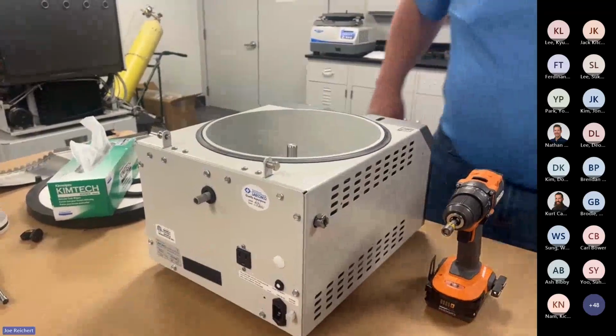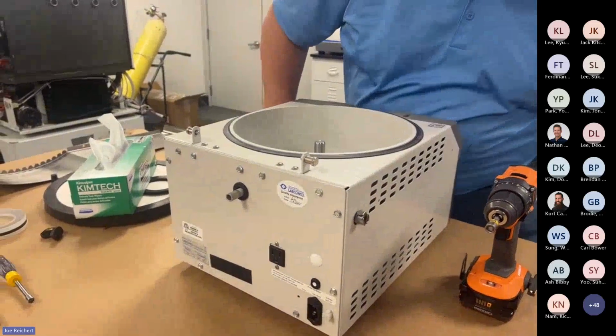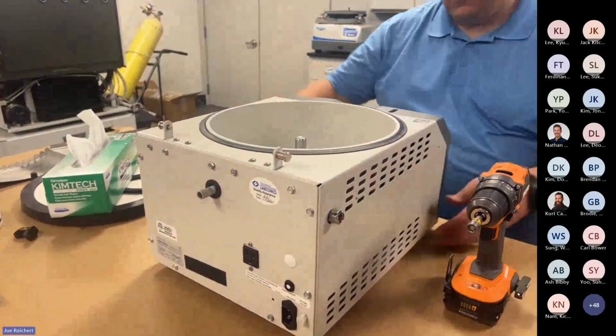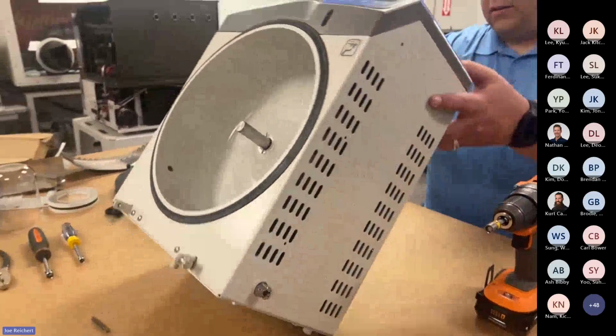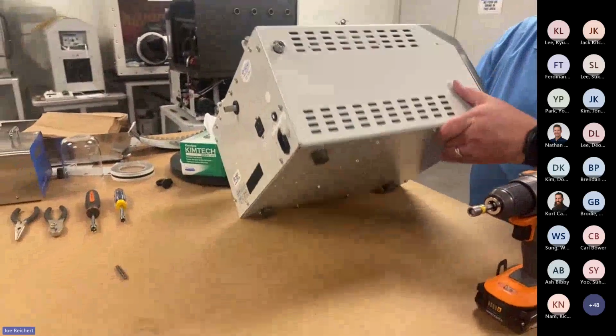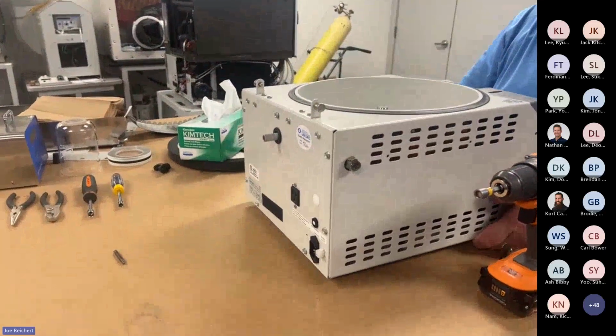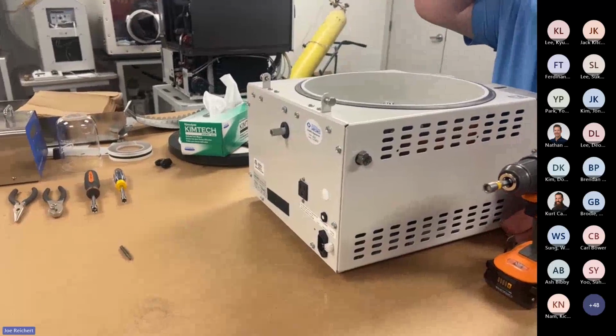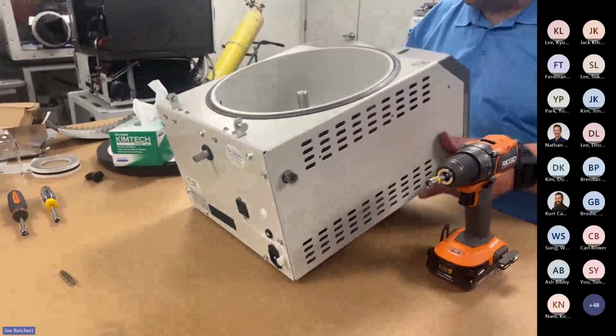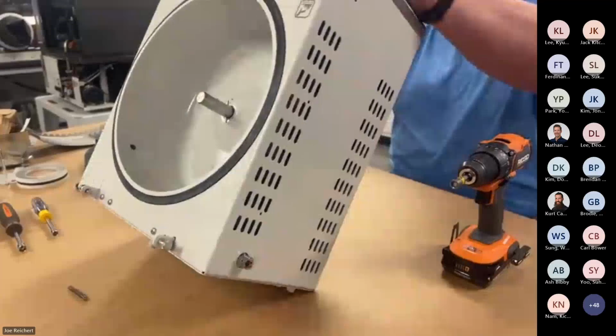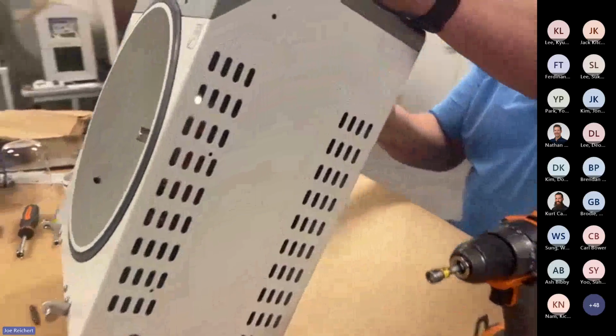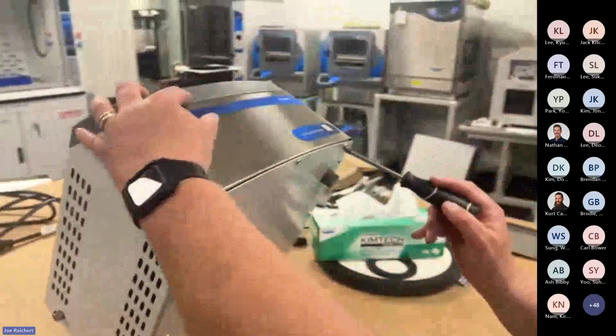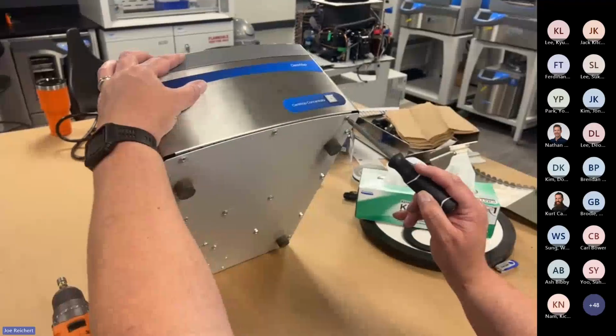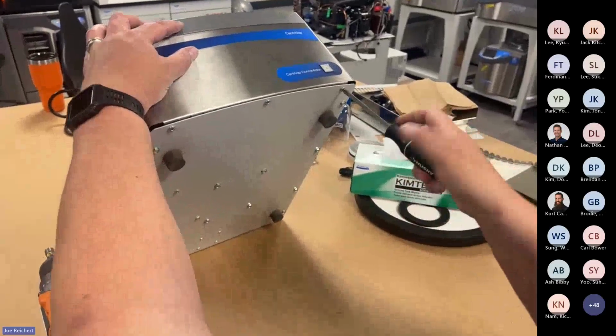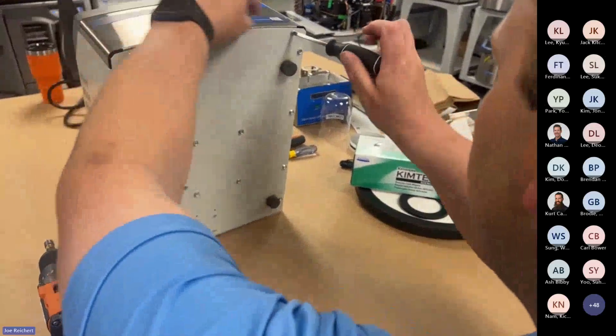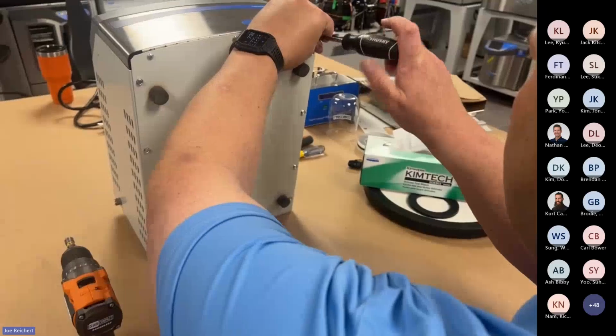and since these units don't have any refrigeration in them, at least this one doesn't, I can tilt it any way I want to, and it doesn't really matter. Nothing inside it's going to move or turn or come loose. Now, if you had a refrigerated unit, obviously you wouldn't want to do that. But there are 3 Phillips head screws up underneath the front edge. Set the unit on its backside.